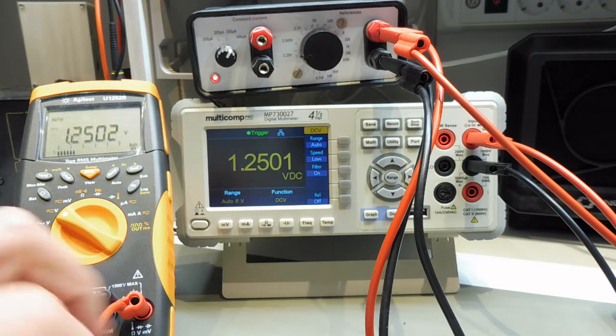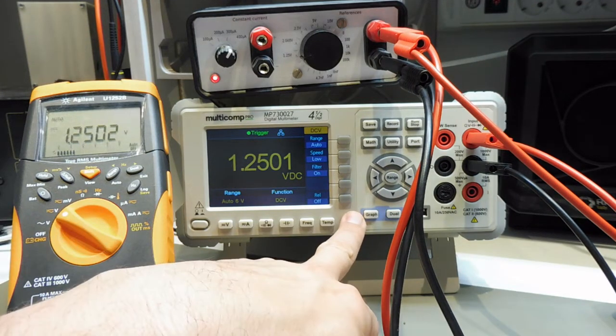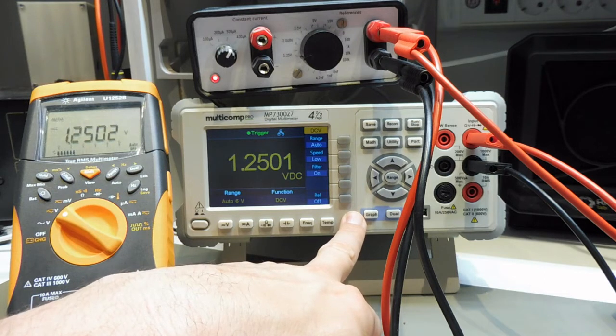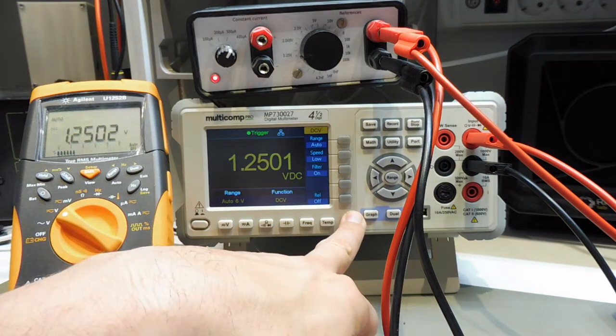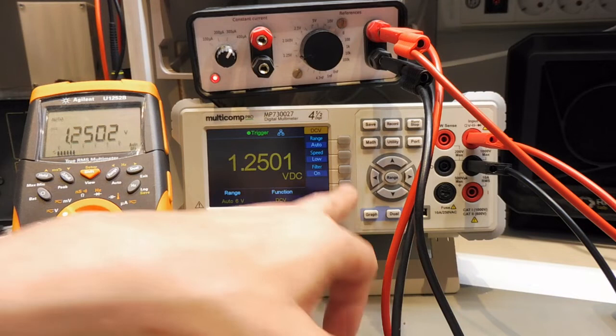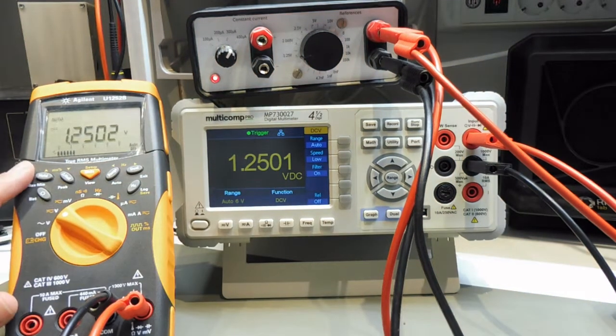One thing to note here is that the multicomp meter did not come with a calibration certificate, which kind of surprised me. The Agilent here, even though it was way too old, came with a calibration certificate. I think for a meter of this precision accuracy, it should always be provided, so you know when you get the meter that someone has checked it is within its specification.